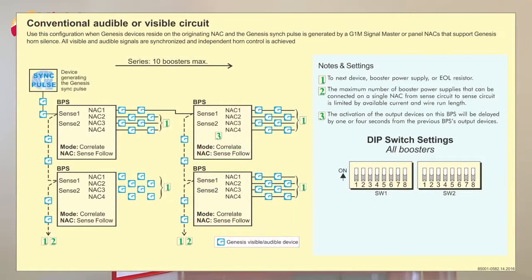Our next configuration will be based on configuring the control panel NAC circuits as the Genesis NAC type. When using the Genesis NAC type on the control panel, all of the switches on the booster panel should be placed in the off position. This is because the control panel will generate the sync pulse for your horn strobe circuits.